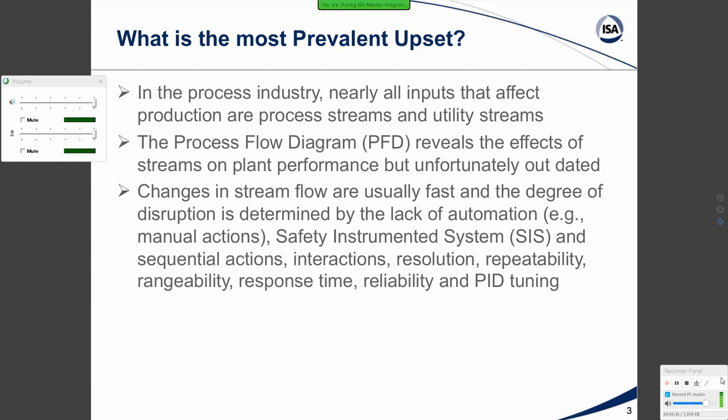Not discussed here, but one of the techniques that's been used, particularly in drum level control, because they're using feed forward there, in terms of ratioing feedwater flow to steam flow, but they end up getting into rangeability limits because they're using DP measurements in particular. So what they do is when they get to the point where the flow measurement rangeability is no longer sufficient at that low flow, they switch to a calculation made on valve position.